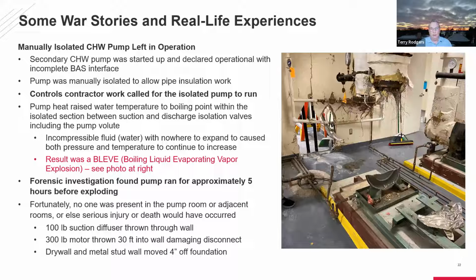But from a control standpoint, what happened was the pump was not taken out of rotation. It was just assigned to the last rotation. So we had 3 pumps and needed 1, and it was made the emergency pump. And then the BMS failed in that it was still working, but it was no longer sending remote annunciations out. So nobody knew that because they weren't paying attention and didn't realize they weren't getting any more remote annunciations.